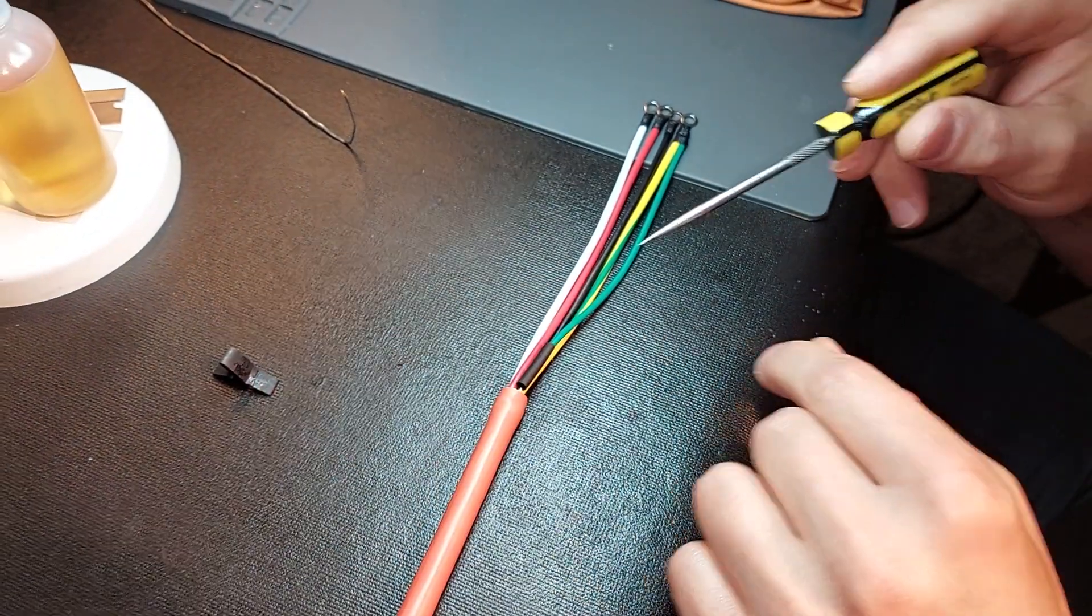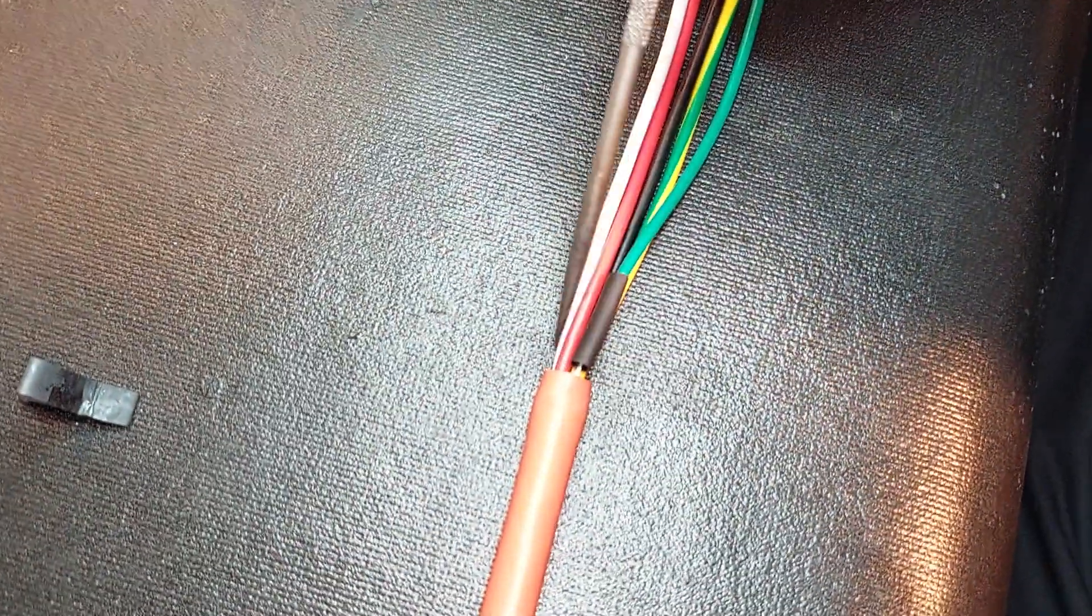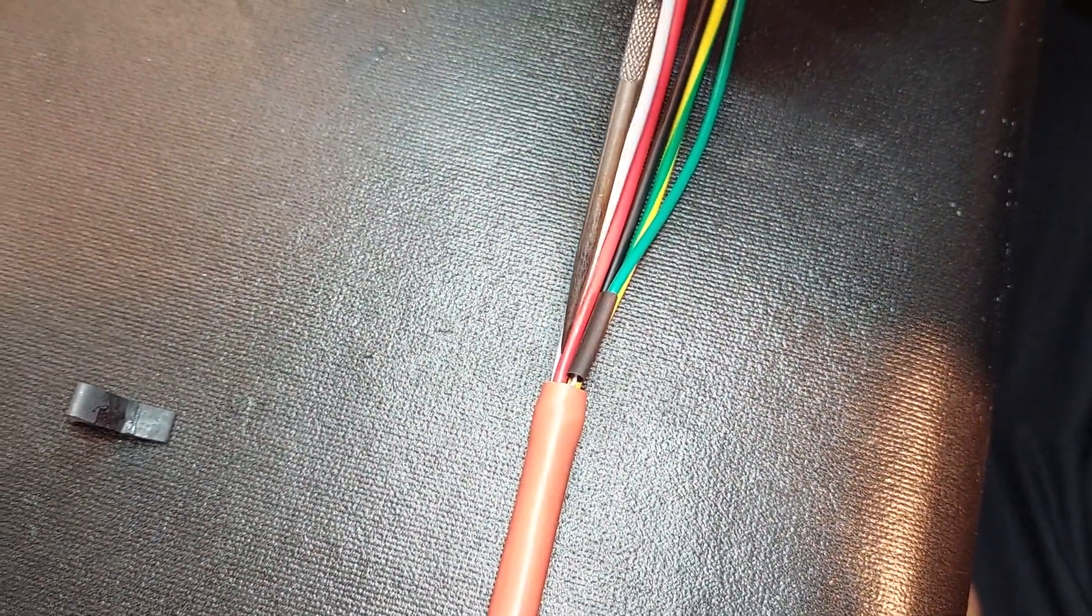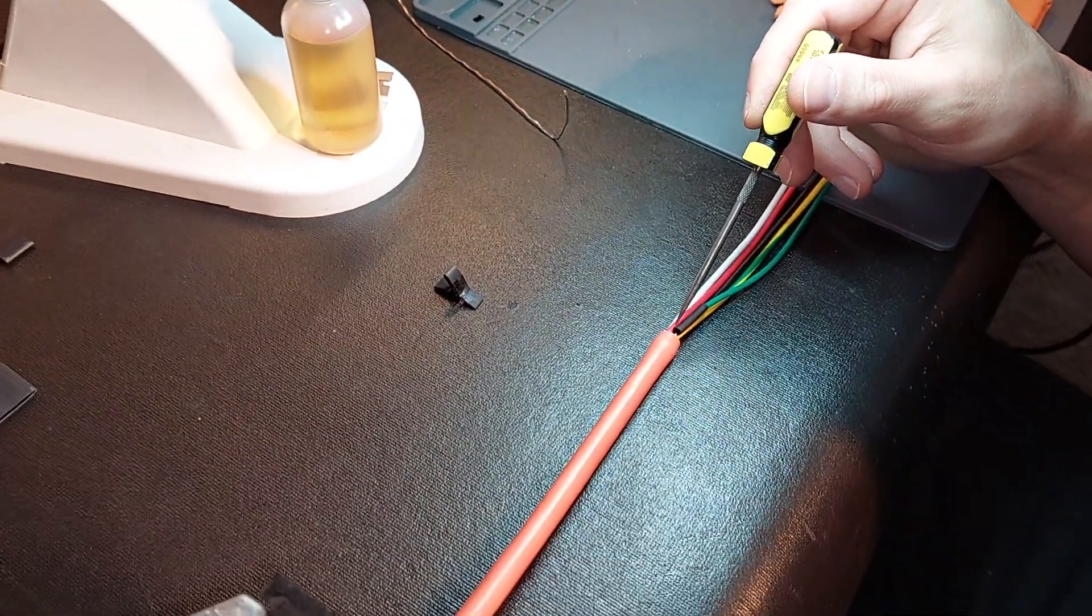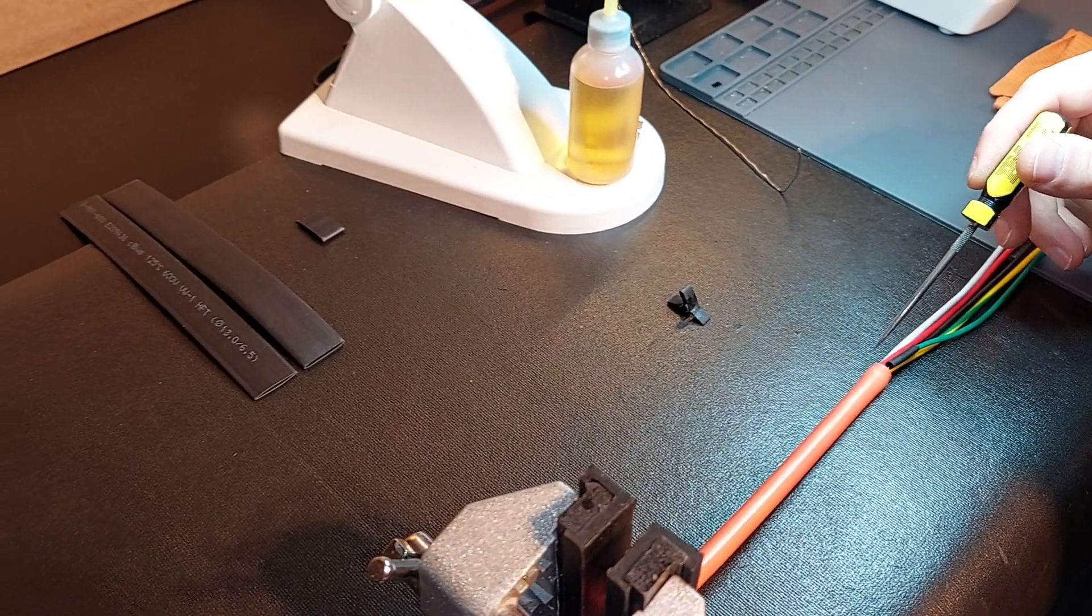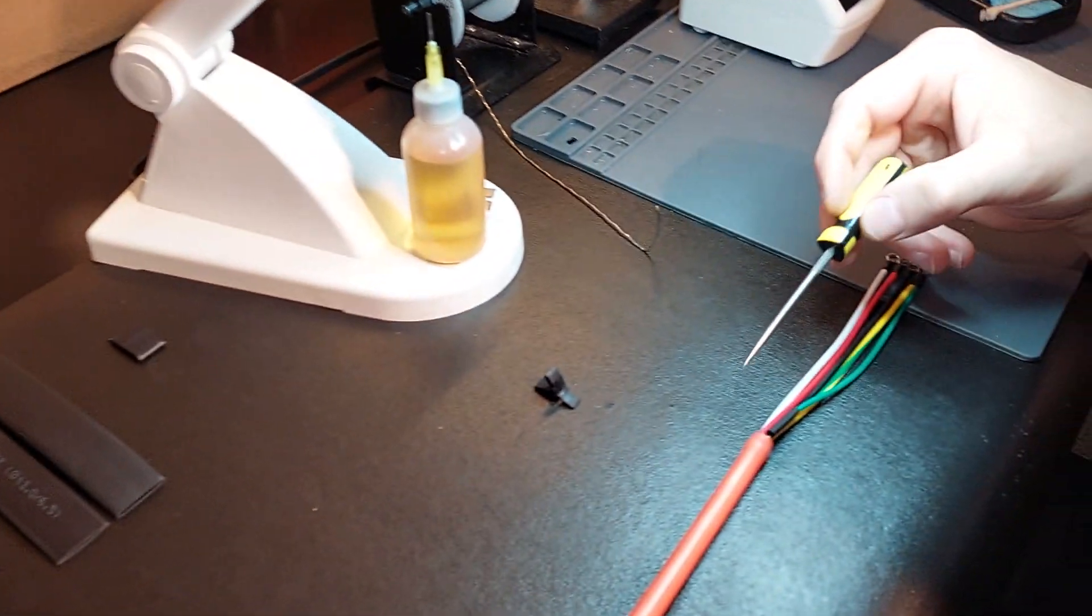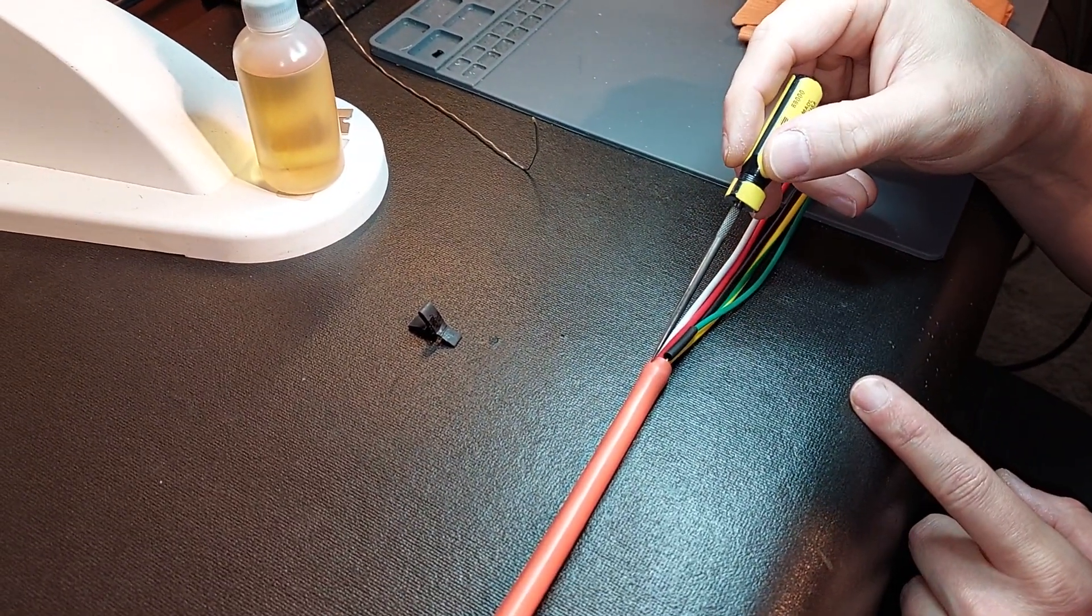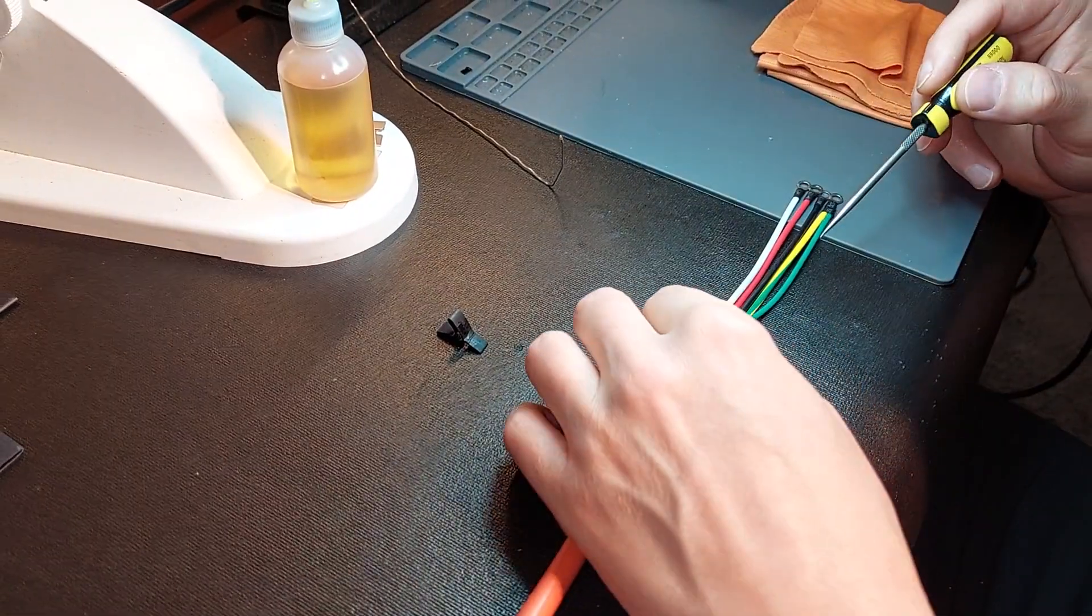You see no protruding tin-braid copper coming through the cable at all, which you shouldn't see. I still see that being done. The idea is to remove all conductive material from being exposed at all. I don't care if it's insulated. In best practice, it should be pushed beneath the casing of the cable, and you can see right here, this is exactly what's been done.